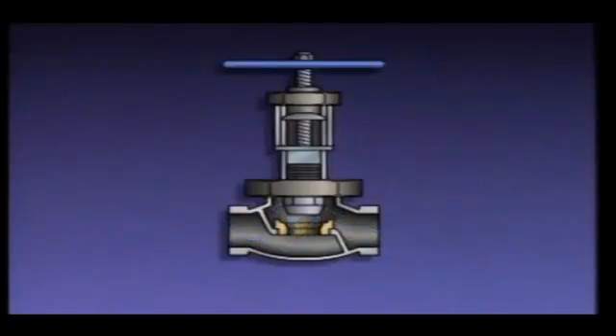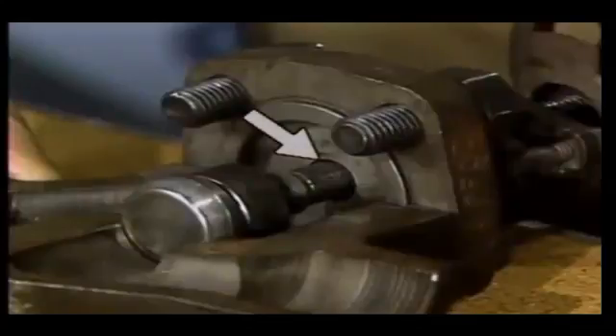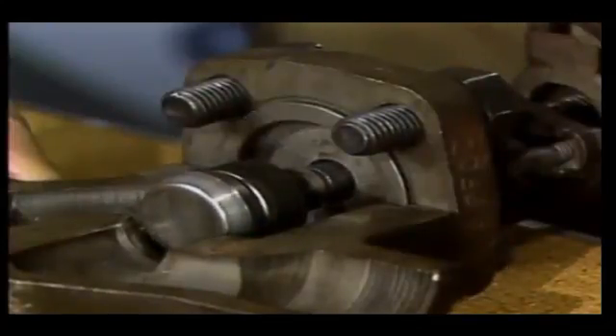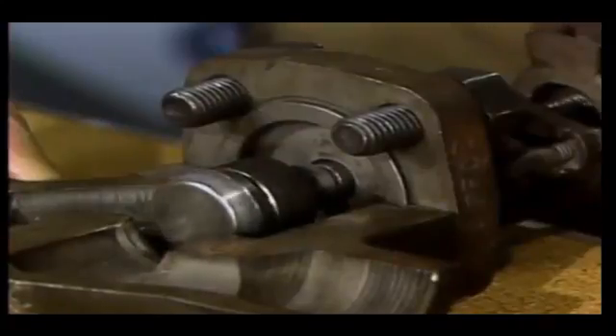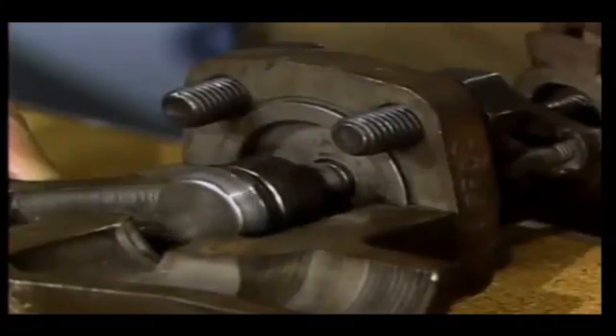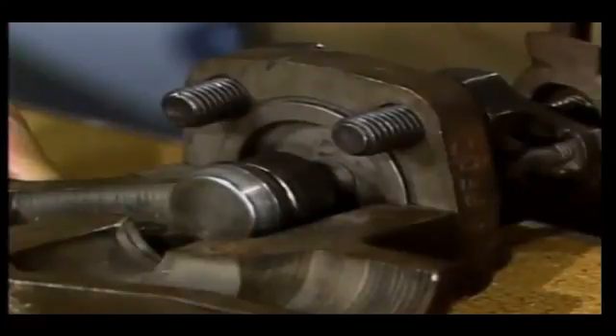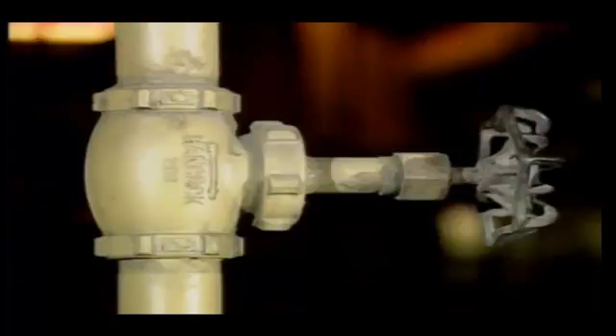In addition to the regular seat, some globe valves have a back seat. If we look inside the bonnet of a globe valve that has a back seat, we can see that when the valve is fully open, the top side of the disc seats against the back seat. This prevents the packing from being constantly exposed to piping system pressure and reduces the likelihood of a packing leak. You can usually recognize a globe valve by its globe-shaped body.